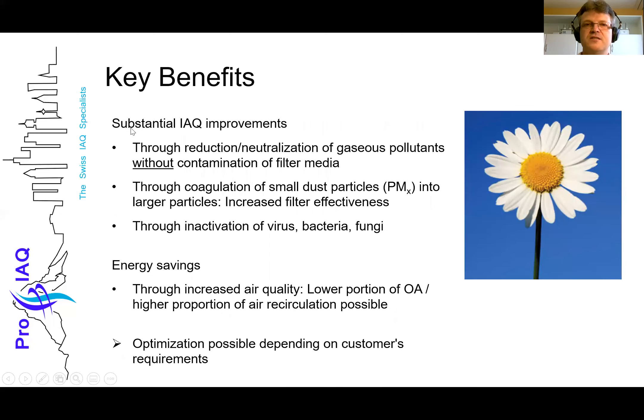The benefits are substantial indoor air quality improvements because we reduce and neutralize pollutants and inactivate viruses and bacteria. Plus, we have energy savings — because we increase the air quality, we can lower the outdoor air intake. In the Middle East, we have done installations where we lowered the fresh air proportion from 100% to 50%, which means the load on the chiller is lowered by more than 50%. It's basically a license to print money.